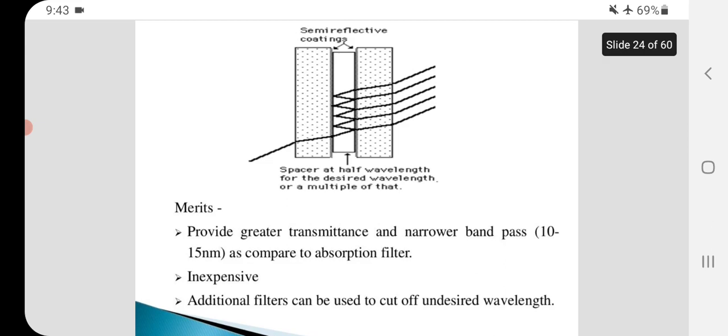These filters have a band pass of 10-15 nanometer with peak transmittance of 40-60%. These are the diagrams of semi-reflective coatings. Merits provide greater transmittance and narrower band pass compared to absorption filter, inexpensive. Additional filters can be used to cut off undesired wavelength.